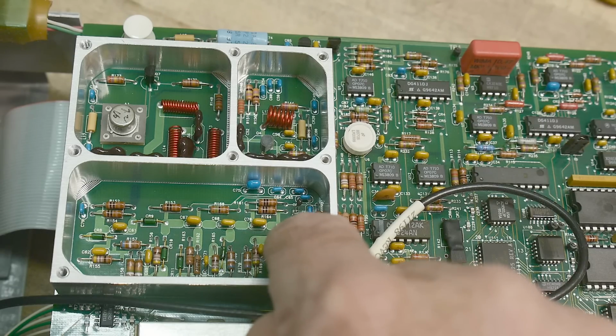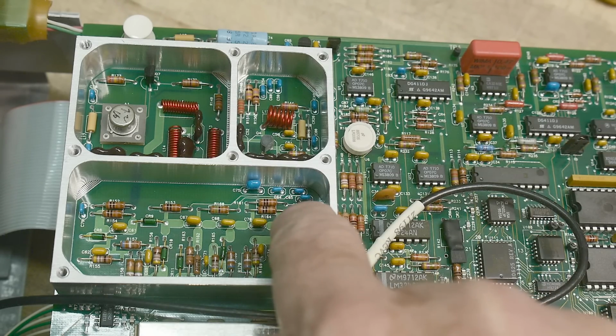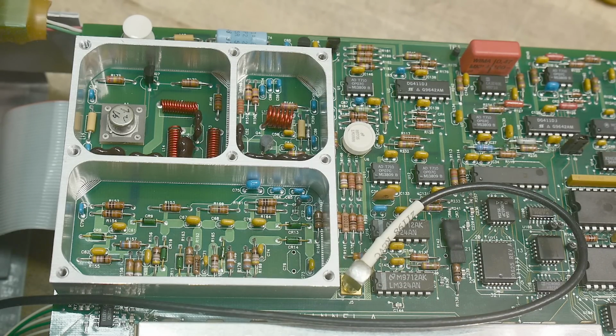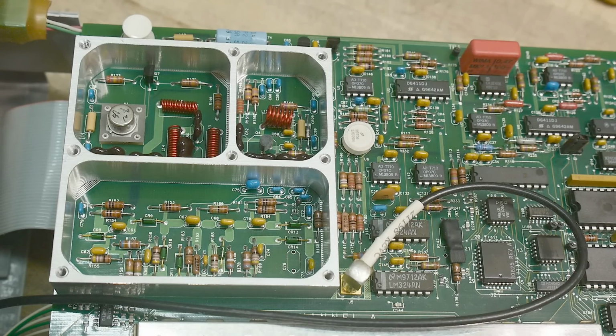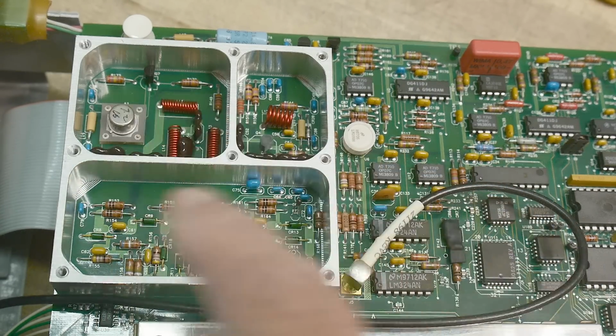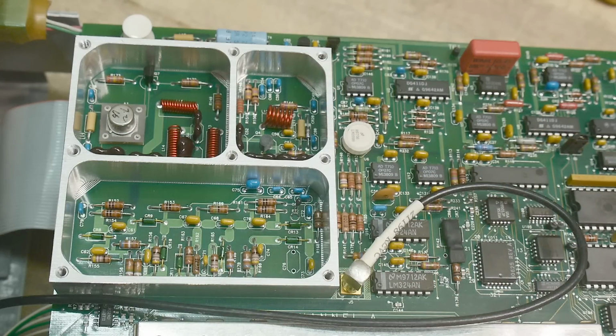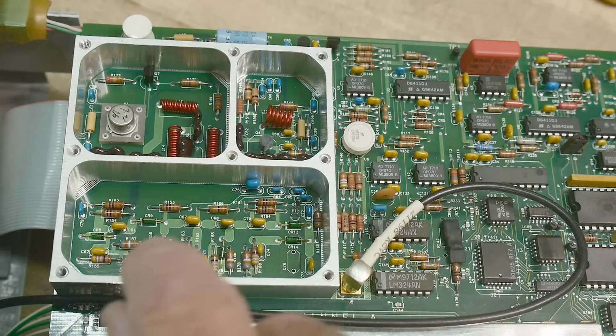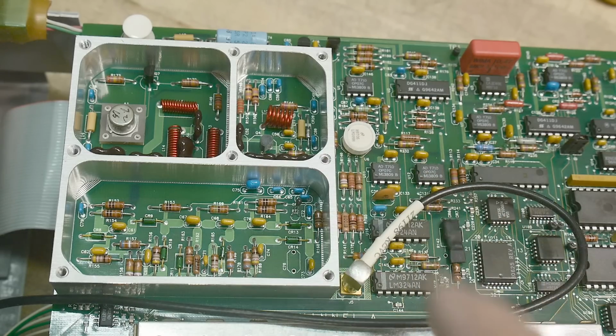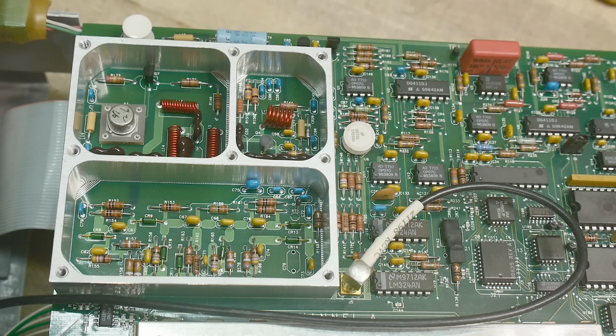Looks like some really, really nice pin diodes in there. They have gold leads on them and everything. And there's a thermistor in there as well. So it's thermally monitored as well. So there's a lot of things going on here, right? So yeah, this is in an oven, right? This is temperature oven. In fact, there's a little box that goes over here when you put this thing together. So this is heated up. So this is both a thermistor to do the measurements and a heating element to hold it constant. So this stays very, very accurate voltage base here, over here, and then you have a thermistor to monitor everything. So yeah, inside the power meter sensor itself is a thermistor, so you can monitor the temperature of the detection diodes on the front of the sensor, and so it keeps those accurate. Yeah, it's very, very complicated, and that's why you get the accuracy you get. So yeah, there's a peek inside.